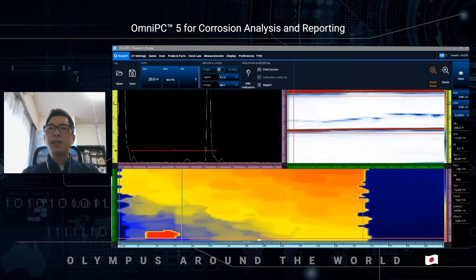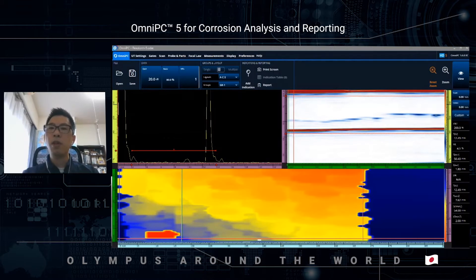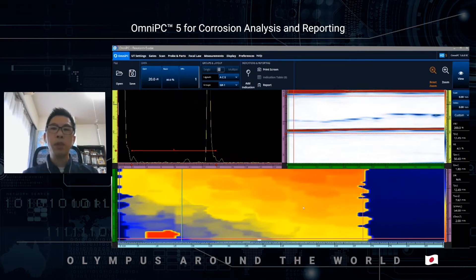The analysis starts from the optimization of the C-scan, which consists of optimization of color palette and optimization of gate position. The color of the C-scan indicates the approximate range of the thickness readings. In this data, it contains color from red to blue, meaning the contrast of the C-scan is optimum between the thinnest part and the thickest area.